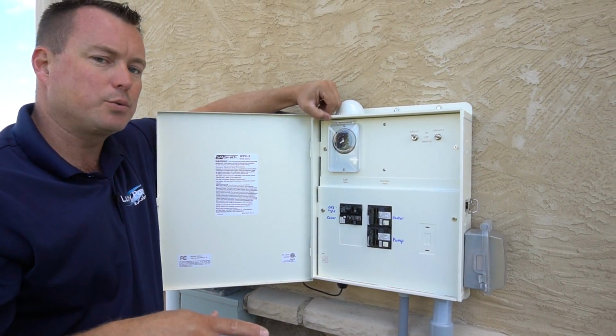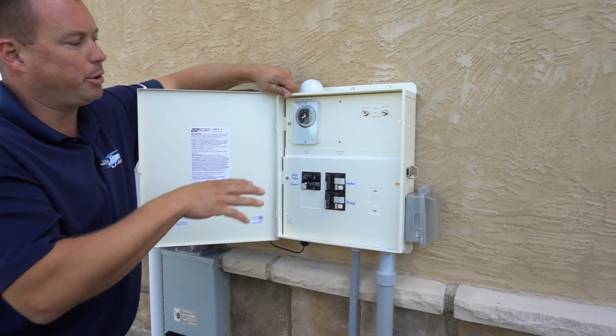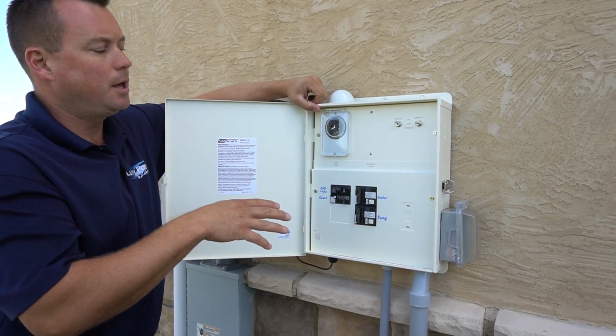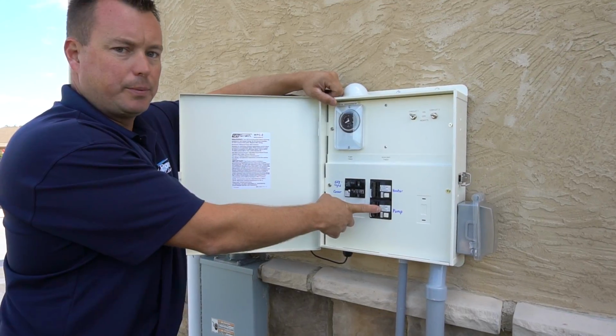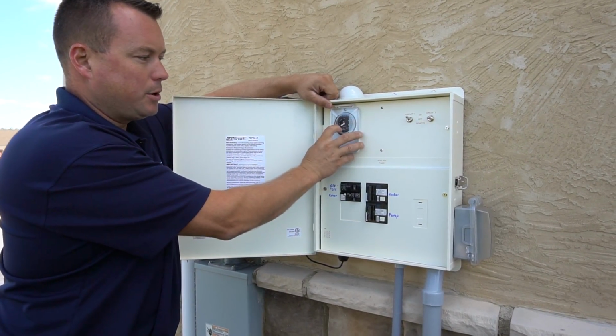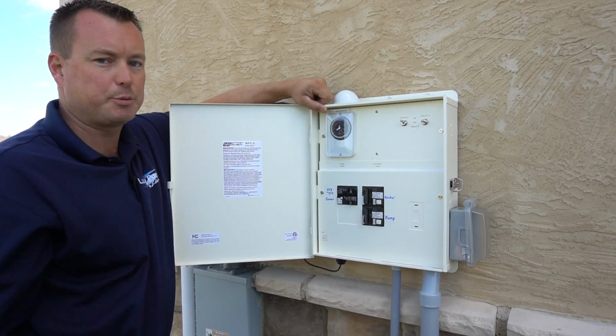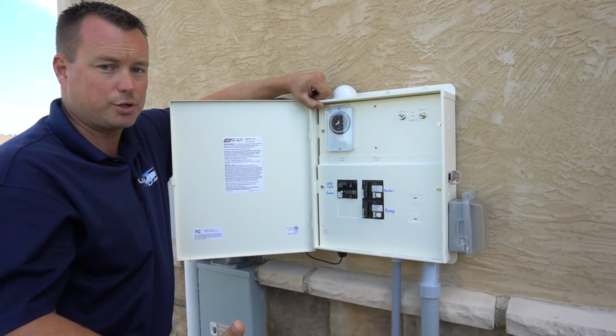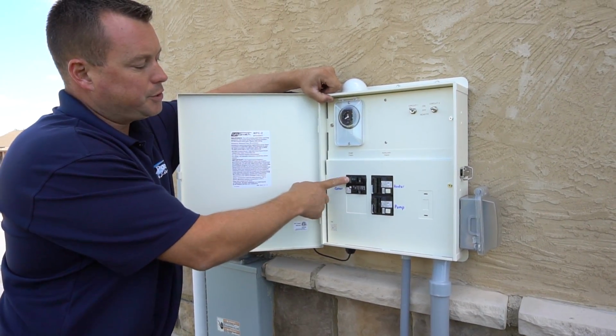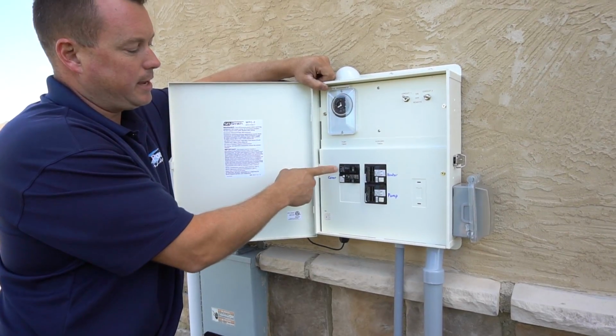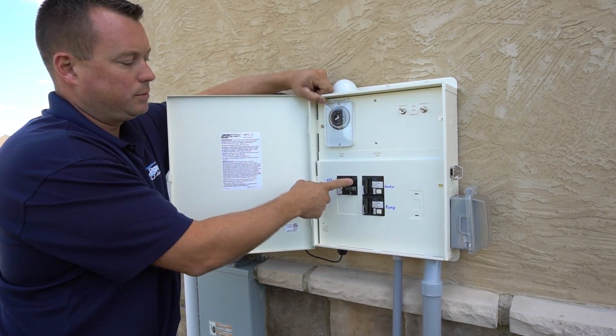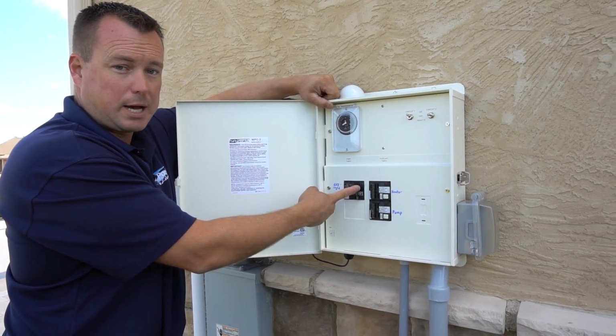One of the gotchas within the system is the pump. You have a circuit breaker for the pump, but because the timer and there's a relay system behind this panel also have to be engaged for the pump to run, this circuit breaker that controls the GFI and the lights also has to be on for the pump to operate.